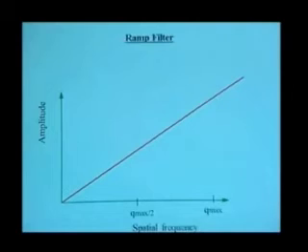Here is an infinite ramp filter that can be applied to the reconstruction. Along the horizontal axis, you can see the spatial frequency. And on the vertical axis, you can see the relative amplitude of the signal passed by the filter. You can see that the filter itself discriminates against low frequencies in favour of the high frequencies. However, with such a filter, we will run into aliasing problems. And so we need to apply the Nyquist criteria to cut off the filter at half the maximum spatial sampling frequency, as we have here.